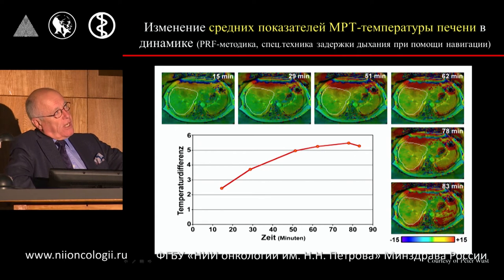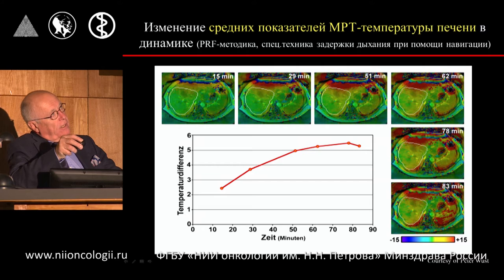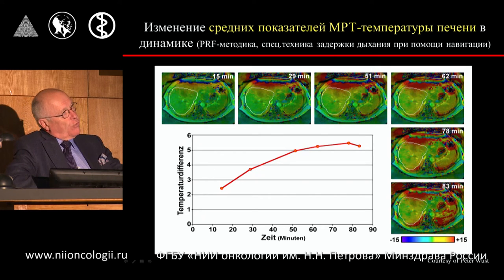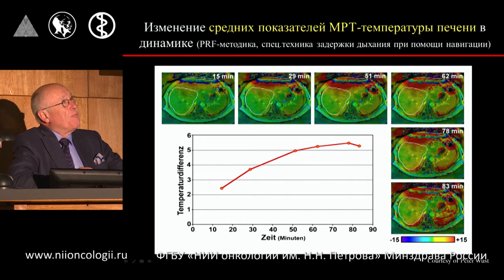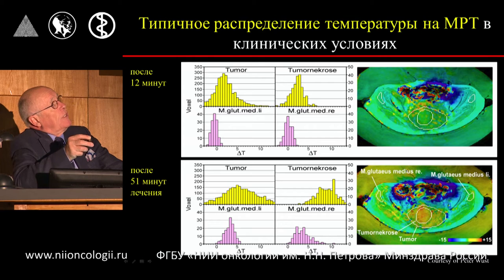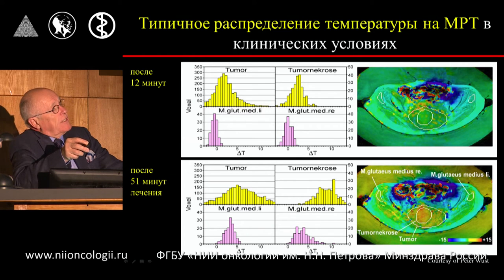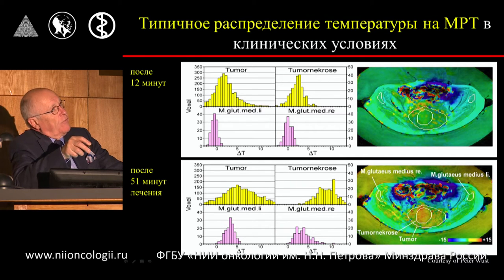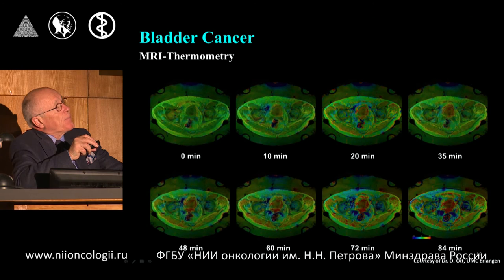We need approximately 30 to 40 minutes in order to receive the optimal temperature inside the tumour. Subsequently, if we deal with regional hyperthermia, the patient needs to be treated for approximately one hour — meaning approximately half an hour to reach the temperature — so the patient must be approximately an hour and a half inside the MR coil. You can see typical distribution of temperature on the magnet in the clinical situation: after 12 minutes the distribution is not homogeneous, but after 51 minutes we have a very good homogeneous distribution of temperature in the tumour.